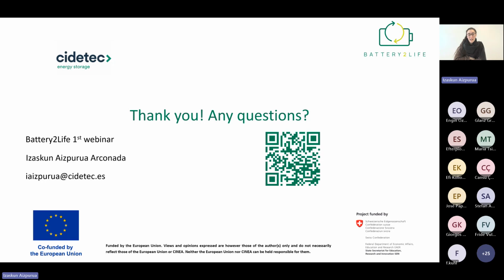Actually, we can define all of those parameters in the tool. You can define your maximum and minimum state of charge, your system voltage, and so on, so it's up to the end user to define those limits. But we usually limit the state of charge range to between 10% and 90%, considering the state of health, so it's not related to the initial full capacity but to the actual capacity, adjusted to the real state of those battery units.